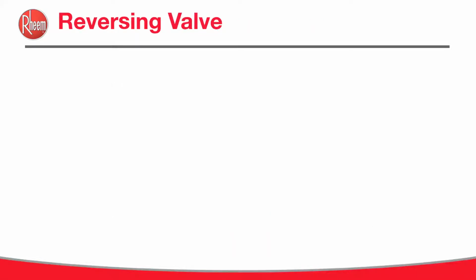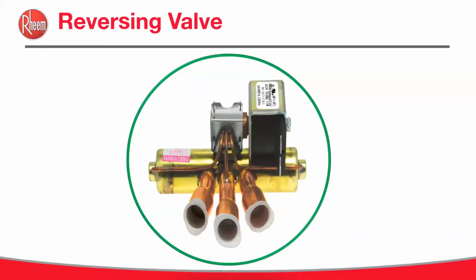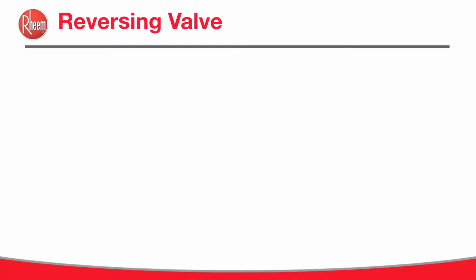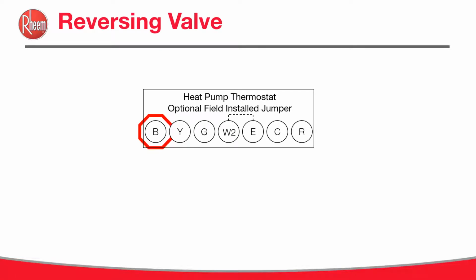Also, all Rheem and all Ruud heat pumps, when de-energized, are in the cooling mode. That's right, we're in the cooling mode when we're de-energized, whereas other manufacturers, when de-energized, are in the heating mode. So what does this mean, you ask? Well, this means you need to ensure you are connected to the B terminal, not the O terminal, if you're using a legacy thermostat. And that's a standard 24-volt thermostat.